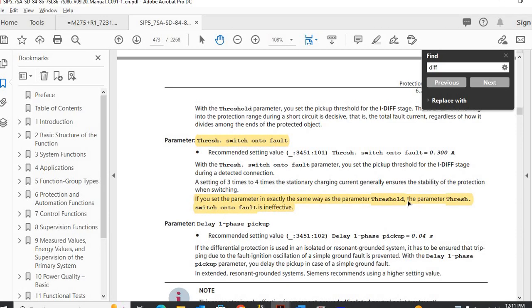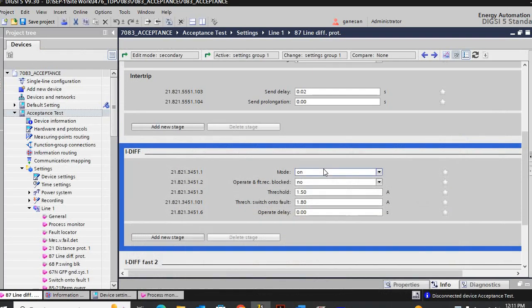As per the manual, if the threshold value and the threshold switch-on-to-fault value are both the same, this is inactive. So we need to give a value more than the threshold value. Now the setting is okay.